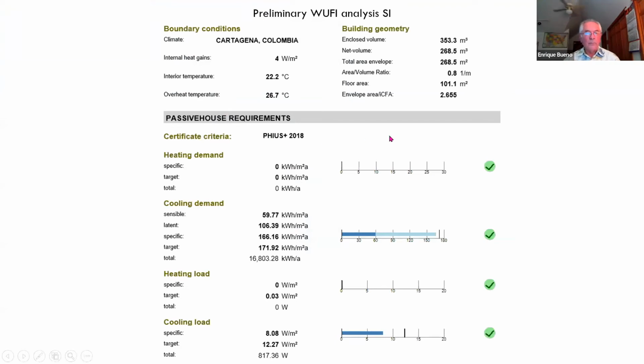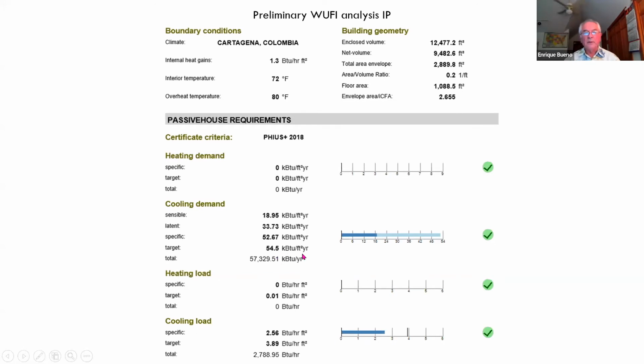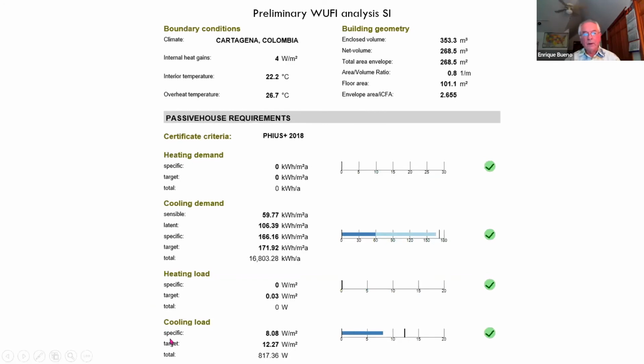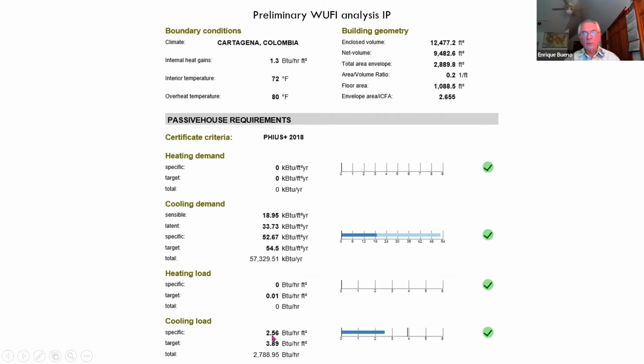And these are the preliminary WUFI results that show the target of 171.92 kilowatt hours per square meter per year, which is 54.5 kBTUs per square foot per year. And the specific cooling load is going to be 8.08 watts per square meter, or 2.56 BTUs per hour per square foot. So for the 1,076 square feet, the total cooling load would be 2,755 BTUs per hour, which the smallest available non-duct mini split of 9,000 BTUs per hour can handle well and provide the additional dehumidification shortfall of the Minotair.